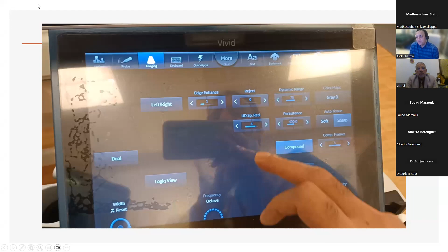It might be that your machine and the probe that you're using is a convex probe. So again, rather than try and fiddle with the settings, the question is, can you reduce the width, improve the penetration of the sound waves to give you a better image? Can you play with the frequency to increase or decrease it? Now, naturally, if you're using a convex probe, which is kind of 8 to 6, then a frequency of 8 is going to be the highest frequency that you can use if it's the cranial ultrasound probe. But we will talk about that, and I will show you images of how to interpret with it. I would say just use your machine.